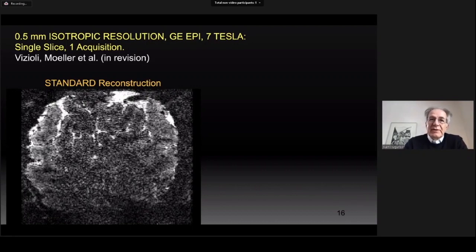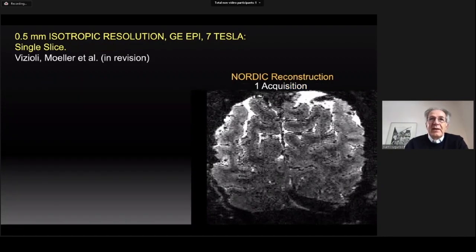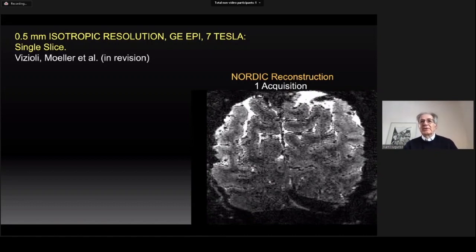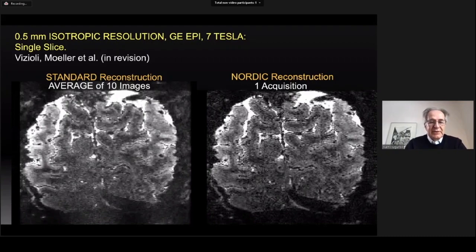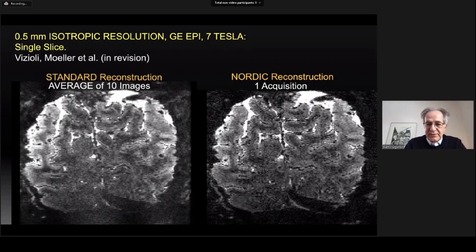this single image reveals that SNR is too poor to provide meaningful functional maps. NORDIC improves it tremendously, as shown here. We can evaluate the improvements by comparing the NORDIC reconstructed single image with the standard reconstructed image of the slice with multiple acquisitions added together. Showing 10 averages of the standard images, these look very similar — so we are achieving approximately the equivalent of a 10-image standard acquisition in the single NORDIC image, without image blurring.